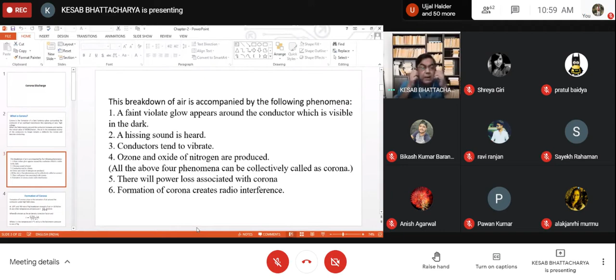Next, let us discuss formation of corona in a slightly different manner. Actually, formation of corona is due to ionization of air around the conductor under high field stress, which we have already discussed. Now, at 20 degrees centigrade and 760 millimeter of mercury pressure, that is standard temperature and pressure, the breakdown strength of air is 30 kV peak per centimeter. At any other temperature and pressure, it should be 30 into delta, where delta is the air density correction factor.